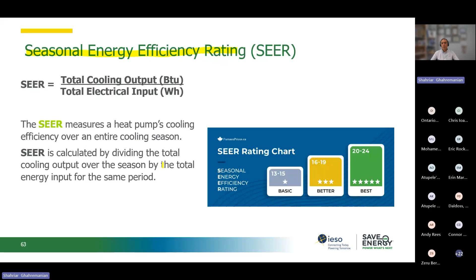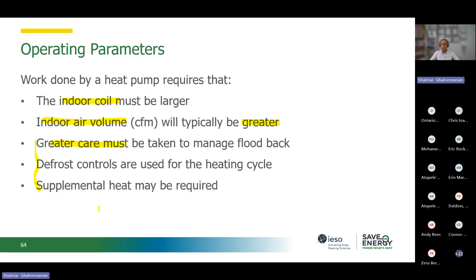So the work done by the heat pump requires all of these. The indoor coil typically sometimes needs to become larger. The indoor air volume maybe becomes greater because the heat pump needs to work a little bit more, and greater care must be taken during the managing of the flood back and those kinds of things. But these are things that are on the contractor that we hire, that we ask to come and design, or basically size, the heat pump for our facility.